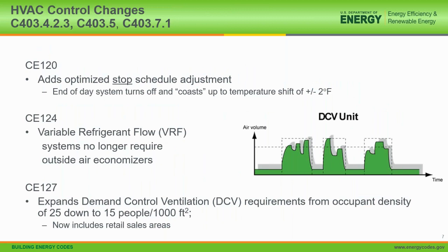We've got several other things. Optimized stop has been added. So we're probably familiar with optimized start, that will vary the warm-up time or cool down time in the morning for a building before occupancy, so we aren't starting too early. Well, this says that we can let the temperature float in the building up to 2 degrees plus or minus for the last, say, half hour or hour of occupancy. And this is compatible with ventilation requirements, which do allow a lag period or an averaging period, a period of time that you can not be actively ventilating the space, but because the space has a large enough volume, it's deemed to be adequate for ventilation. So that's an added requirement. It's pretty much a no-cost requirement that's available in most DDC systems.